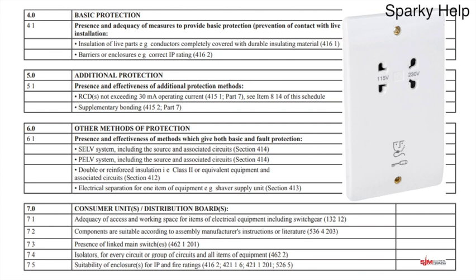Sometimes people think they are an SELV, but it's not, because if you look, the output voltage is 230 volts and 115 volts. So actually it's a low voltage output, but it is separate. It is a separated supply, so it's similar to the SELV, but it's not the extra low part, it's just separate from earth. So on these, hence they're allowed in bathrooms within the prescribed zones, obviously.